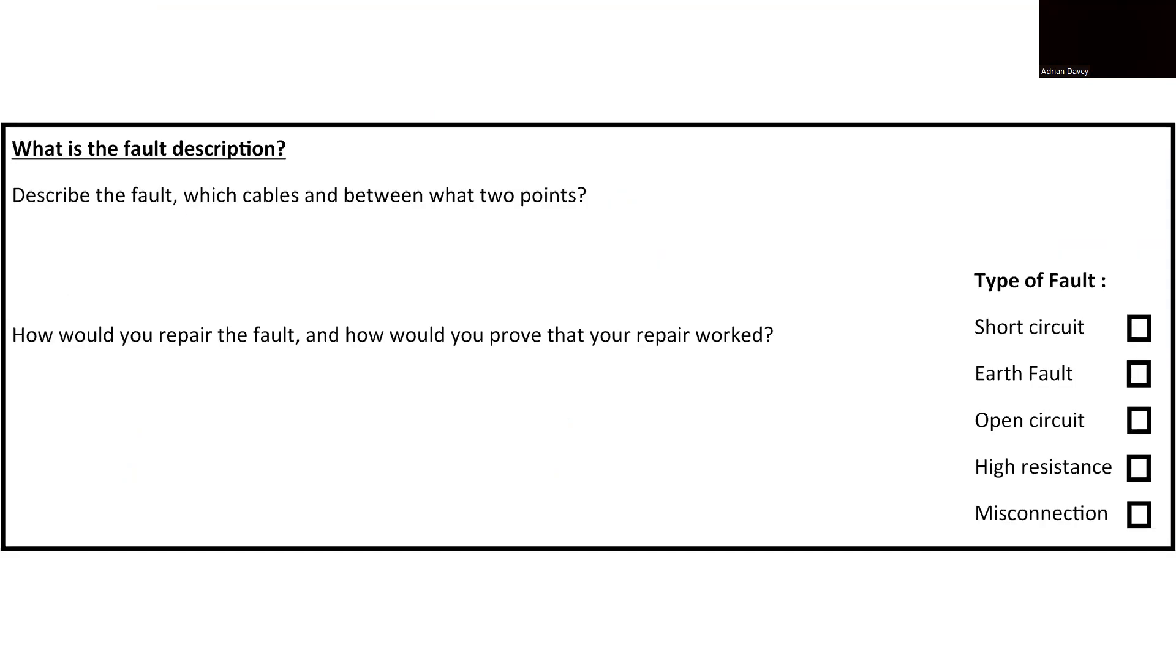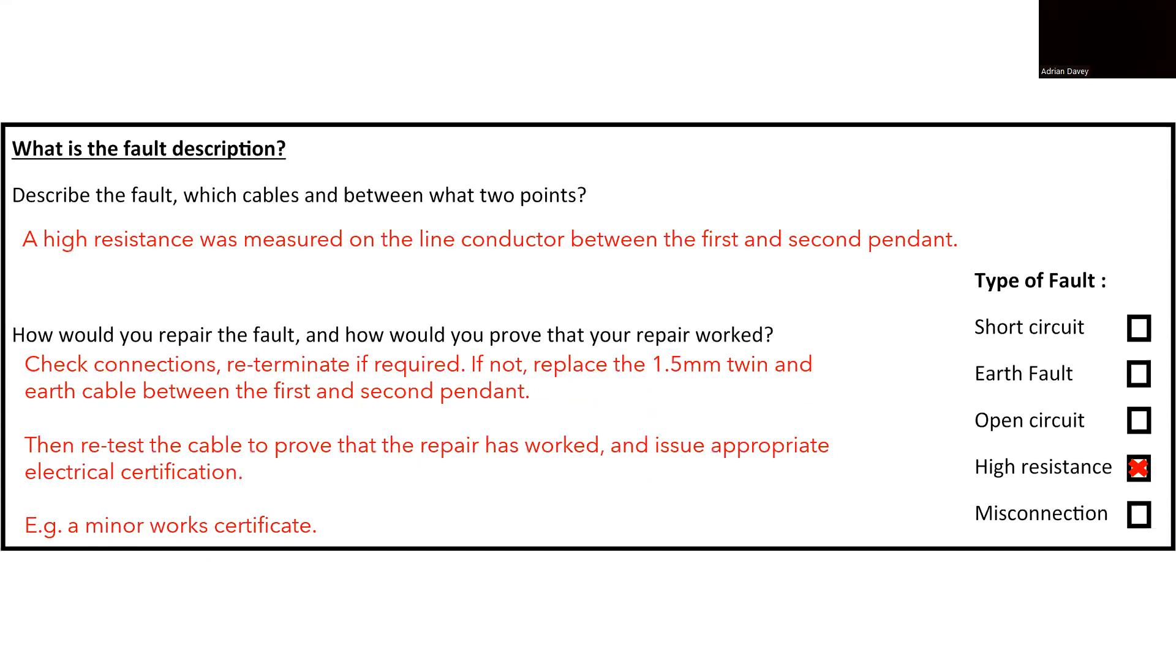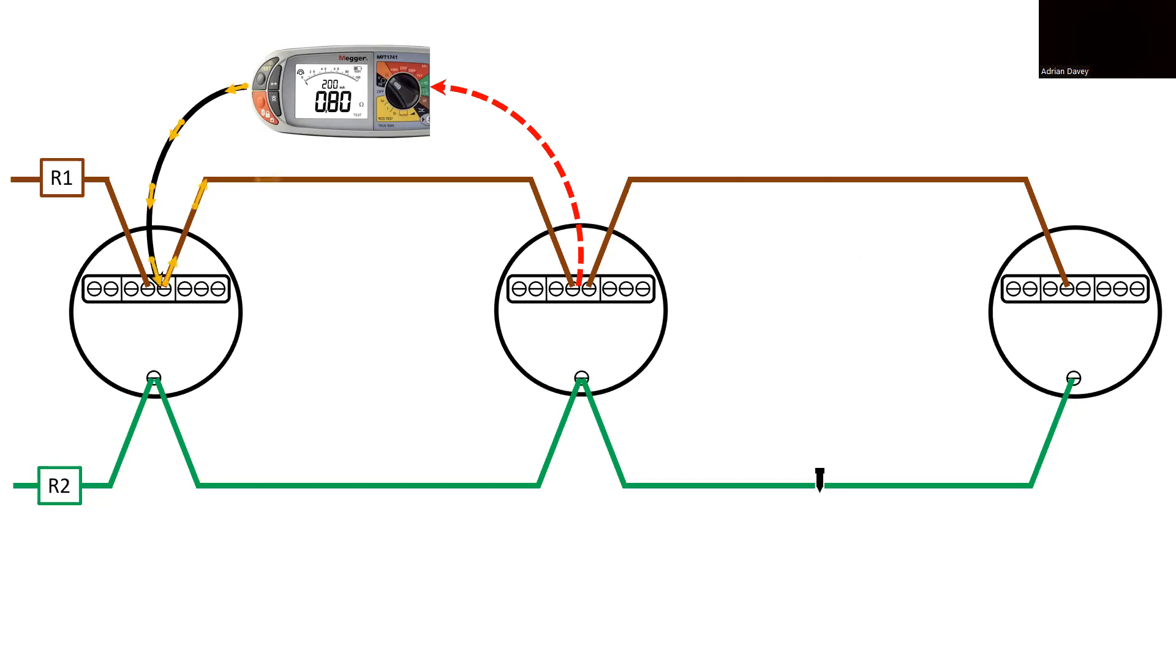If you are required to write a report on the fault to provide feedback to the person who requested the work, the report could be structured as follows. A high resistance fault has been identified between the first and second pendant on the line conductor. This issue allows us to classify it as a high resistance fault. To rectify this, we can replace the 1.5 mm twin and earth cable running between the first and second pendant since the line conductor is an integral part of this cable. After completing the required repairs or replacement, it is essential to conduct retesting to confirm the success of the repair. This step is critical for both verifying continuity and resistance, and without retesting, there would be no reliable means to determine the effectiveness of the repair when a minor work certificate may be required.